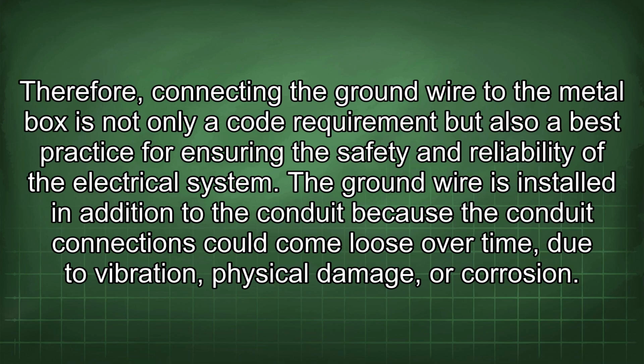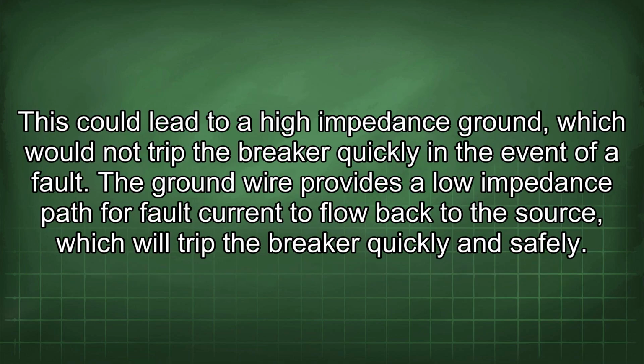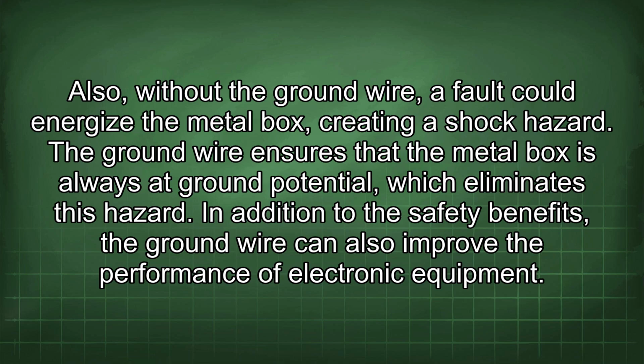The ground wire is installed in addition to the conduit because the conduit connections could come loose over time due to vibration, physical damage, or corrosion. This could lead to a high impedance ground, which would not trip the breaker quickly in the event of a fault. The ground wire provides a low impedance path for fault current to flow back to the source, which will trip the breaker quickly and safely. Also, without the ground wire, a fault could energize the metal box, creating a shock hazard. The ground wire ensures that the metal box is always at ground potential, which eliminates this hazard.